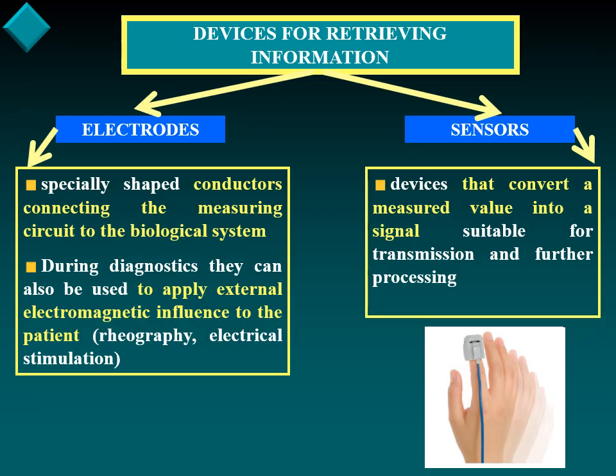To obtain information about the parameters of a biomedical system, it is necessary to have a complete set of devices. It can be a measuring instrument, display devices, a recording device, but we will focus in detail on the pickup devices. An information retrieval device is a device that is directly in contact with the system itself. And these include electrodes and sensors. Electrodes are special-shaped conductors connecting a measuring circuit with a biological system. When diagnosing, they can be used not only to remove an electrical signal, but also to bring an external electromagnetic influence to the patient. They should be fixed, removable, durable, and not irritate the biological tissue.